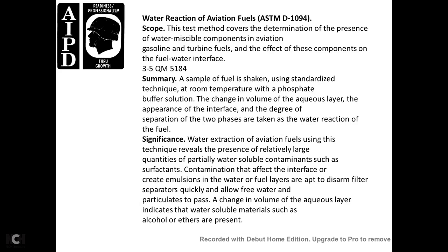Water Reaction — Aviation Fuels, ASTM D1094. Scope: covers determination of the presence of water-miscible components in aviation gasoline and turbine fuels and their effect on the fuel-water interface. Summary: a sample of fuel is shaken using standardized techniques at room temperature with a phosphate buffer solution; changes in the volume of the aqueous layer and the appearance of the interface indicate the degree of separation of the two phases.